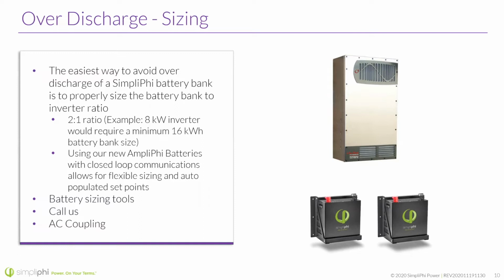The easiest way, and I'm just talking about the Phi battery here to start, to avoid over discharge of the Phi battery is to properly size the battery bank to the inverter ratio. So 2-to-1 ratio, meaning if we have 8 kilowatts of inverter, we would require a minimum 16 kilowatt hours for the battery bank size. That means that if the inverter pushed out all of its 8 kilowatts, and not all inverters, definitely some are coming around on this, but for the most part, most inverters without comms will not limit their discharge. It's not programmable. It's simply just how much it's going to discharge. And even if it was programmable, you're still relying on the programming of the inverter, which can fail sometimes or change depending on firmware updates.